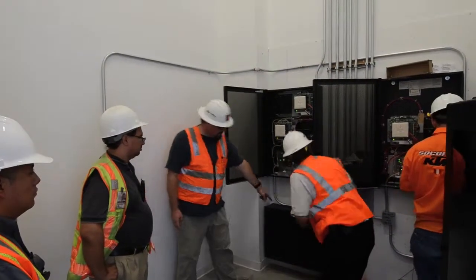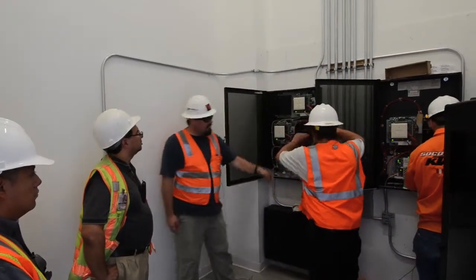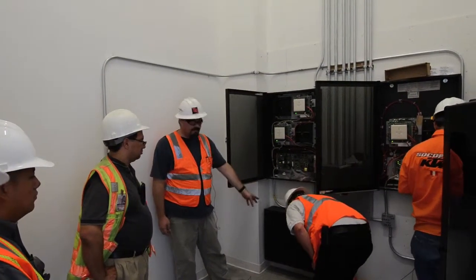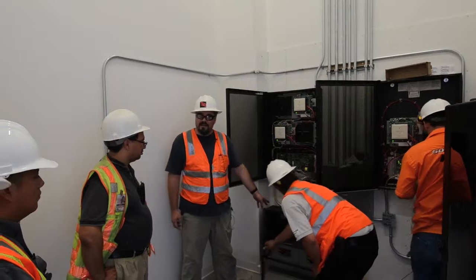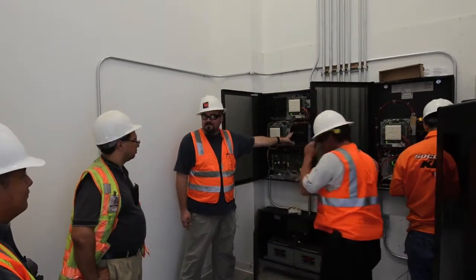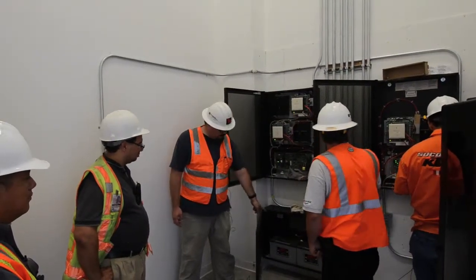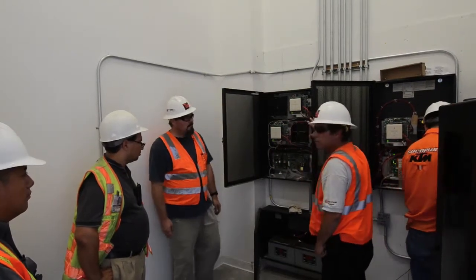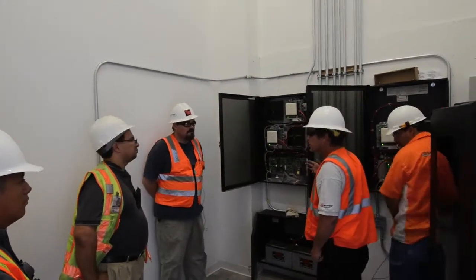However, we've opted to go with, and like we said, the same key will open every panel, same notifier key. And we had to go with 100 amp hour batteries because you have so many. So we couldn't use the little tiny batteries. So these are battery shells. We had to go with the big, deep cycle batteries. And each one of these is capable of supporting a battery charger or charging batteries.